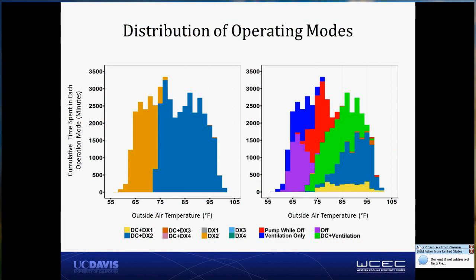One really important thing to note, which I had mentioned a little bit previously, is that there are significant differences between all the different rooftop units on this store. We can see that for the unit on the left, the system runs in DX2 continuously. We're marking out here as a function of outside air temperature the cumulative time spent in each operating mode. So orange shows when we're running in DX2, and the blue shows when we're running in DX2 plus dual cool. The dual cool runs when it's warm enough outside.